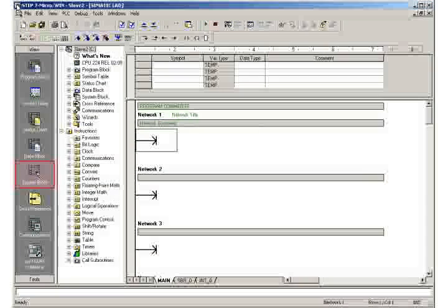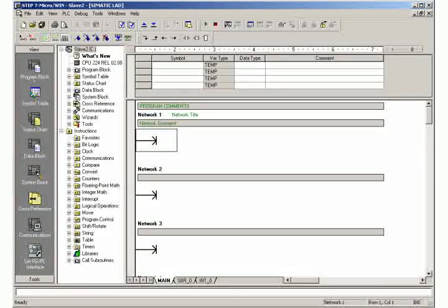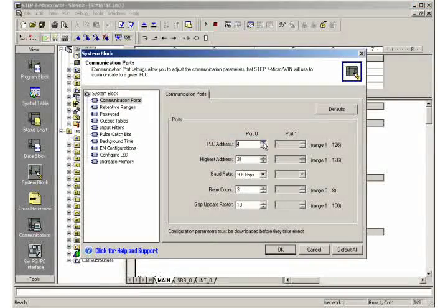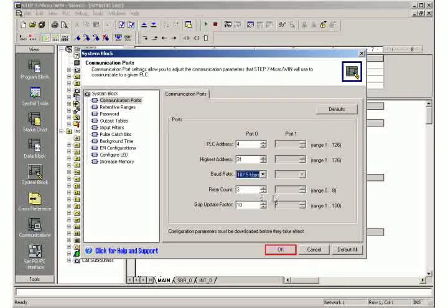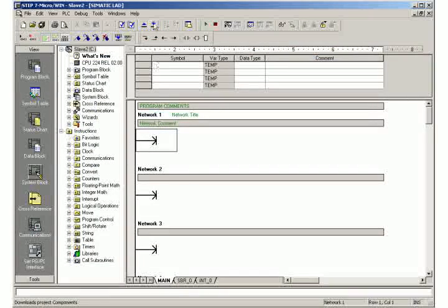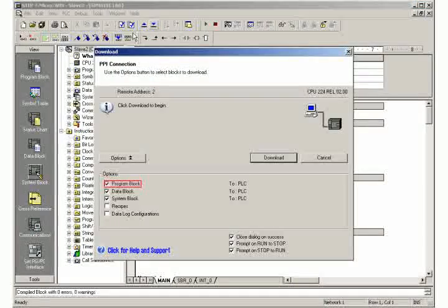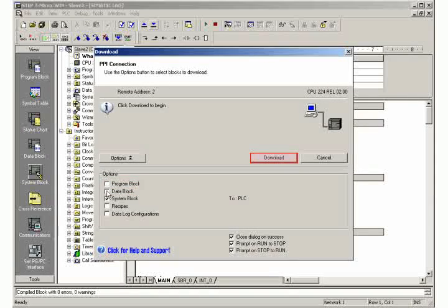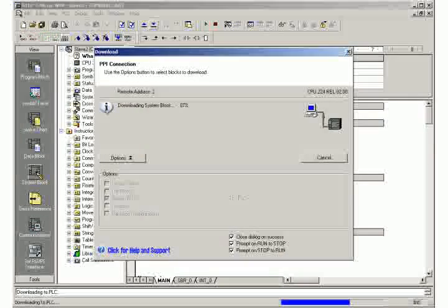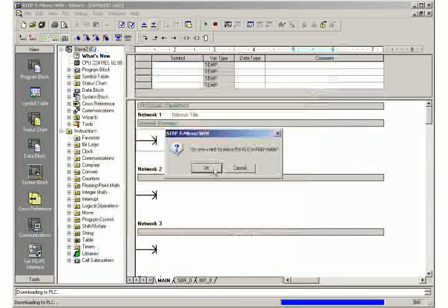In Step 7 Micro/WIN, open the view of the system block. Set the PLC address to 4 and the baud rate uniformly to 187.5 kilobits per second. Load the settings into the PLC. Since for the slaves only the system block contains information, only transmit those to the PLC. Stop the PLC for the transmission, then set it to run mode.